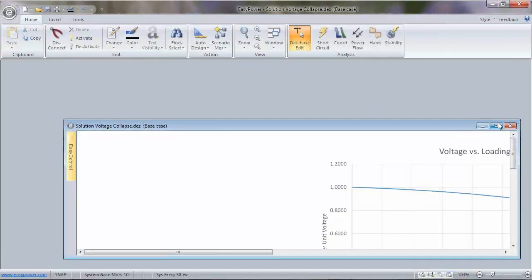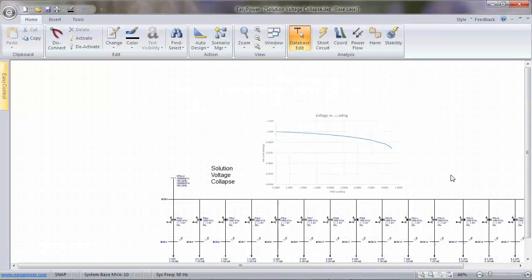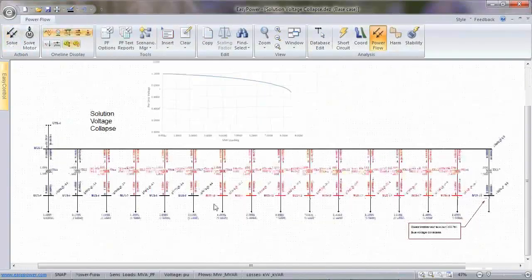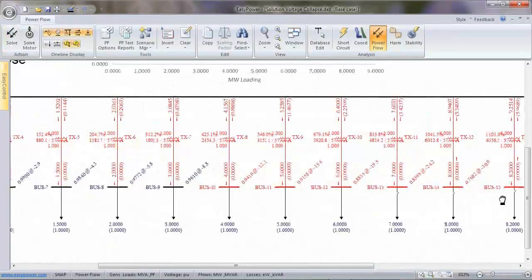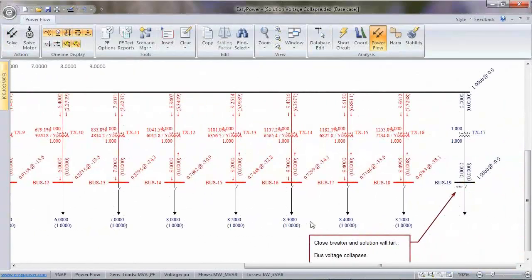What else do I have? I've got these gen and load models we already had in the slides. And just in case you were interested, I do have the voltage collapse solution. If you actually wanted to see it, I put the nice plot in there and everything. If you guys would like to have that case, I plotted the results that happen along here. If you solve the case, you zoom in, you can see how the voltages are dropping and dropping and dropping. And I just kept incrementing this until it finally failed.